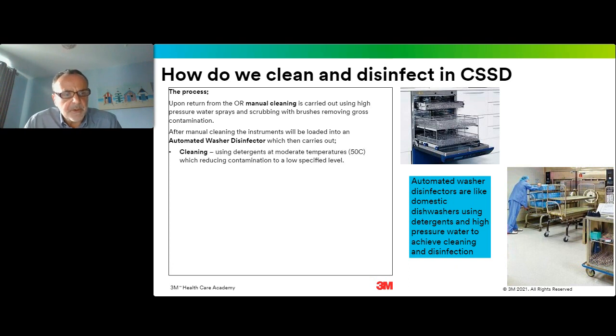And this process will use a cleaning process where maybe the first step is a flushing, where gross contamination is removed with relatively cold water to avoid protein coagulation. And then the next step would be carried out at a slightly higher temperature, 40, 50 degrees C, with the addition of detergents in order to really rigorously remove any residual tissue from the previous operating room procedure.